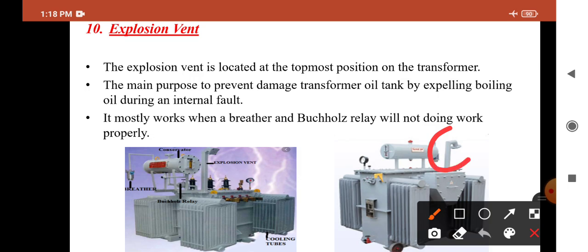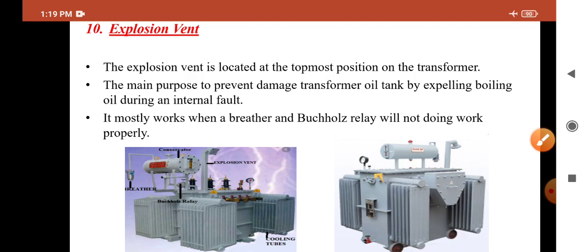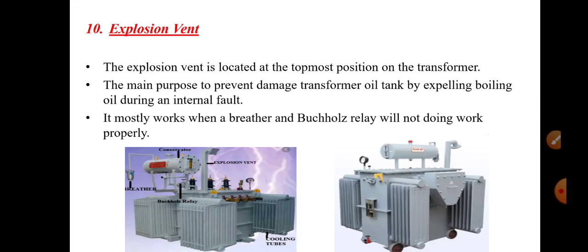The next part is the explosion vent, which is located at the topmost position of the transformer. The main purpose of the explosion vent is to prevent damage to the transformer oil tank by expelling boiling oil during an internal fault. If there is extra heated oil, it is removed through this vent. The explosion vent is used only for emergency purposes — if the Buchholz relay and breather are not working properly, the explosion vent is used.